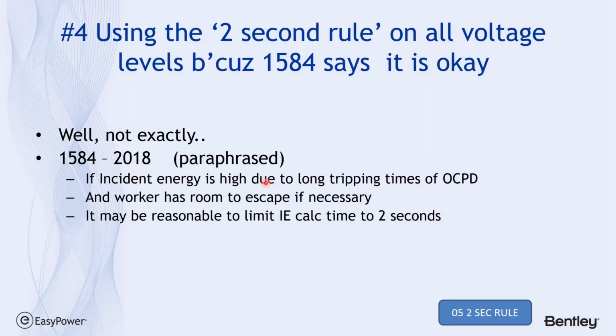And, again, this is a repeat from last year, but frequently I see people send their first round of arc flash calculations with the 2-second rule limiting all voltage ranges that they have in their system. And when the question is why you did that, it says, well, 1584 says it's okay to limit everything to 2 seconds. Well, not exactly.